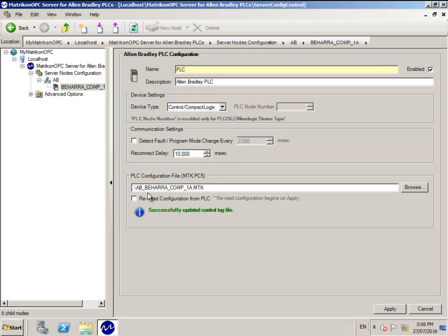The re-read configuration from PLC box must be used whenever you change your program in your PLC. This updates the point validation file with the latest information. Please ensure that the procedure is written for the person responsible for changing the PLC program, which includes this step.